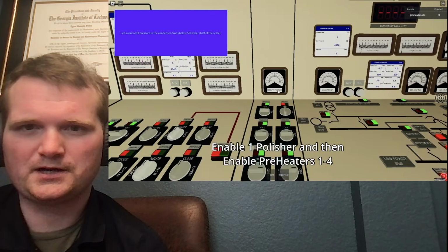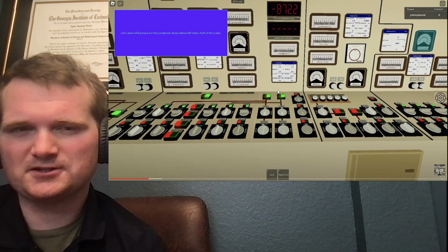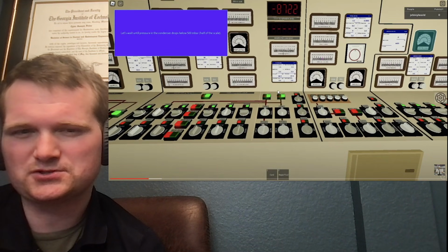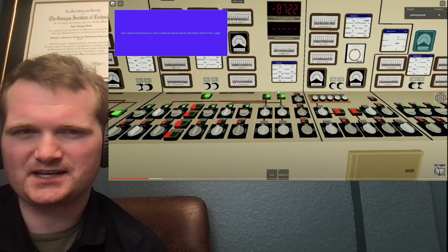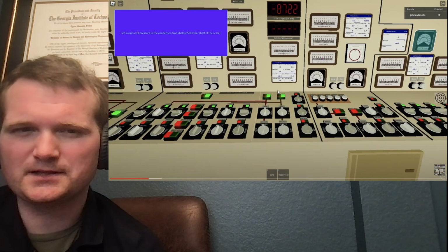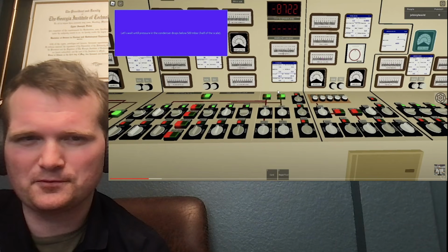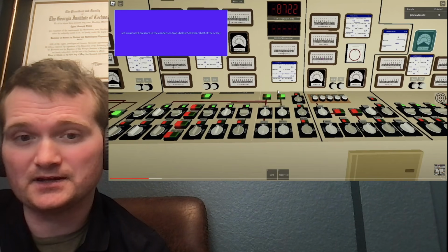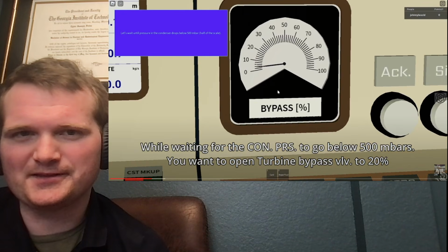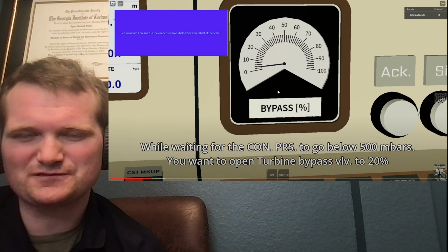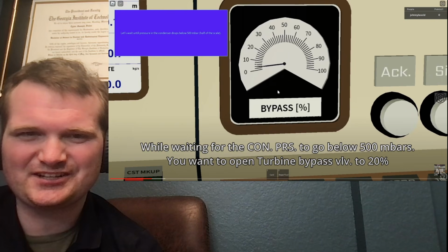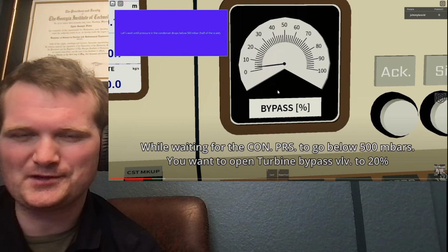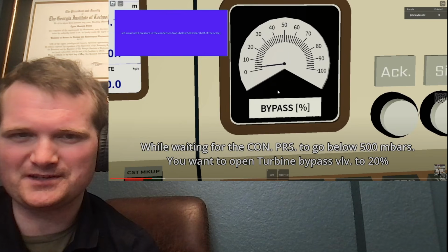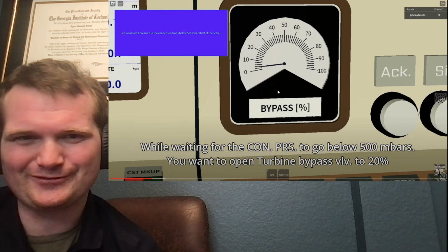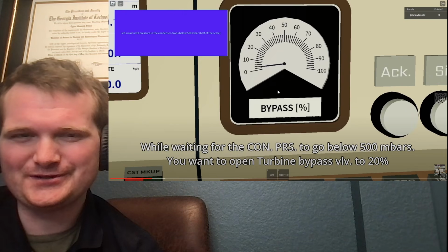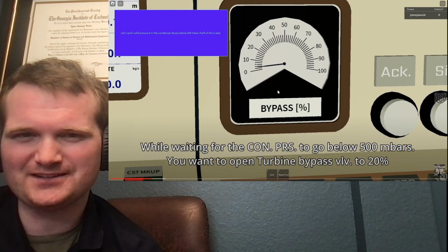So there's your trade-off. Polisher and preheaters. So Polisher is a chemistry control cleanup system, removes chemical contaminants as a means for cleanup and corrosion control. The plant I worked at used a series of demineralizers, below 500 millibars. Yeah, the units I'm used to are in inches of mercury vacuum. You can get it as close to a vacuum as you can. A perfect vacuum would be 30 inches of mercury, and the plant I worked at was right at 29. So you can get these pretty close to a vacuum to make it as efficient as possible.